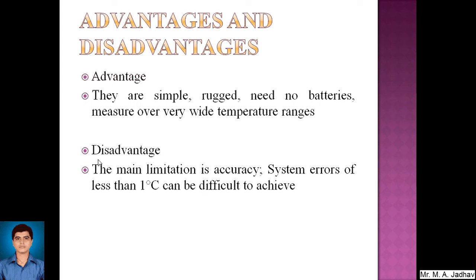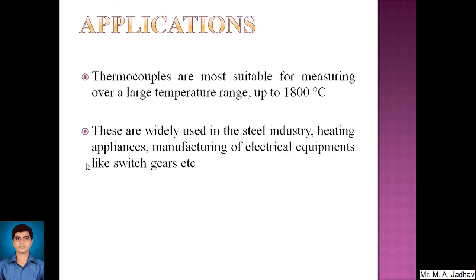The main disadvantage is limited accuracy: the least count of a thermocouple is 1°C, so it can measure 1 degree high or low from the accurate value. If the temperature changes by a small amount — for example from 37°C to 37.5°C — it cannot be detected. Applications include measuring over large temperature ranges up to 1800°C, and thermocouples are widely used in the steel industry, heating appliances, and manufacturing of electrical equipment such as switchgear.